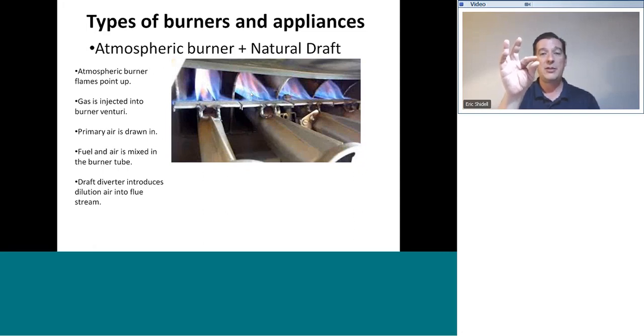As primary air supply is reduced, those flames will soften, they will elongate, they will get a little bit longer. And a good-sized flame is a soft-looking blue flame that is between a quarter of an inch and half an inch tall. If we reduce air supply even further, those flames will get very long. They will get very wavy and wispy, and they will start to mix in with this larger flame corona, and then they will start to get yellow tips, and then we lead to sooting.